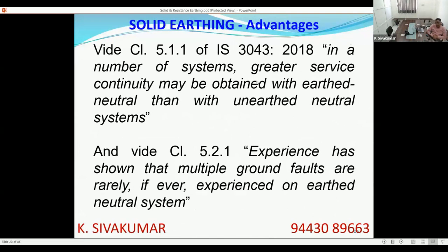Similarly, if you look into the advantages of the solidly grounded system, the Indian standard itself documents the advantages. In a number of systems, greater service continuity may be obtained with an earthed neutral system. Because if you recall, last time we discussed that one of the important advantages of the unearthed system was service continuity. There will not be significant fault current flow because in the unearthed system the neutral is isolated from ground, there is no return path. So there will not be any significant fault current flowing, and the system will not get disconnected because there is no sensing of the ground fault current, there is no tripping of the breaker. So there will not be any service discontinuity. This was thought to be the biggest advantage of ungrounded or unearthed systems.